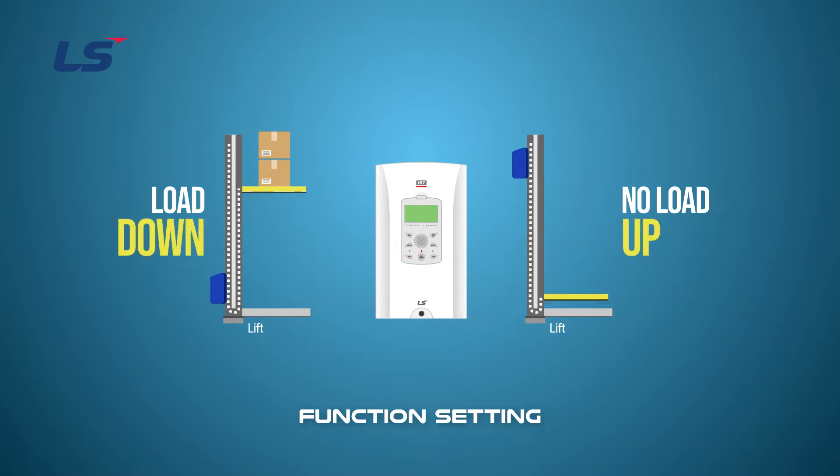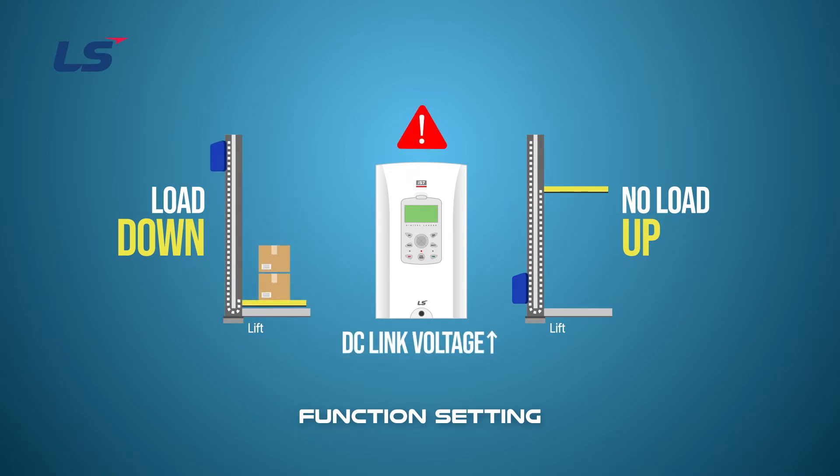Conversely, if it rises under no load condition or falls under load condition, a regenerative voltage is generated in the motor and increases the DC link voltage of the inverter.